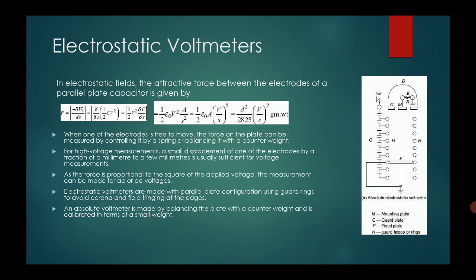For high voltage measurement, a small displacement of one of the electrodes, by a fraction of a millimeter or a few millimeters, is usually sufficient. So here they are measuring the movement of the electrostatic plates when an AC voltage is applied. As the force is proportional to the square of the applied voltage, the measurement can be made for AC or DC voltage. So the electrostatic voltmeter can work for both AC and DC.